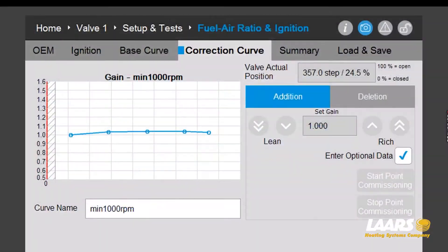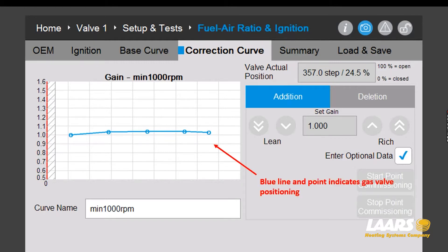Click log in again and be patient — it will log in for you. The login is okay. Our next screen will come up. Here is a screenshot of the gas valve display under correction curve. You'll see a blue line with multiple points, and those points are the gas valve positions. We want to go into each point and check combustion.